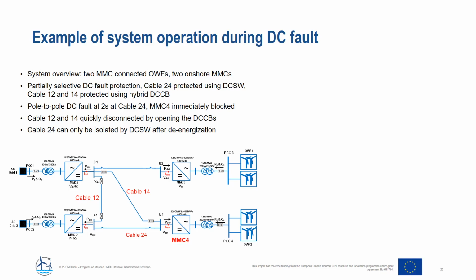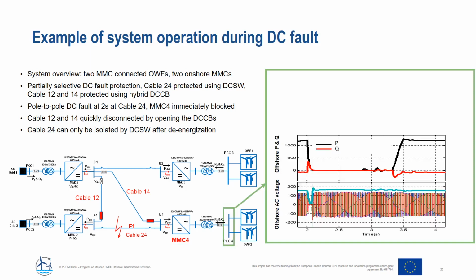Considering a pole-to-pole DC fault at cable 24 at 2 seconds, MMC4 is immediately blocked while cables 12 and 14 are isolated by their DC circuit breakers. However, cable 24 can only be isolated once it is completely de-energized. Now let's look at the sequence and the waveforms at the offshore wind farm system.